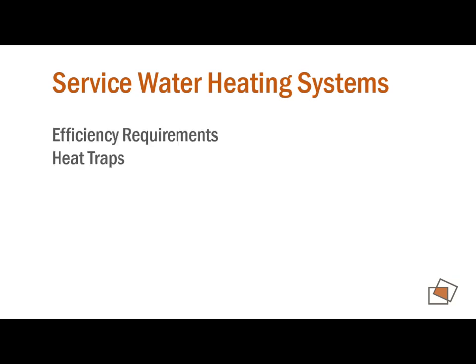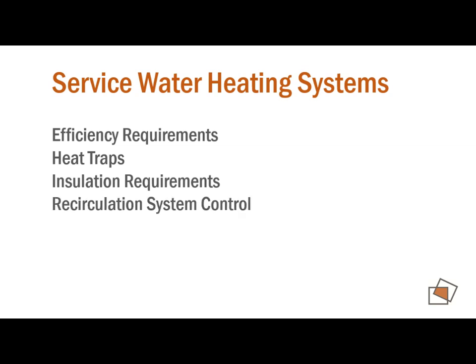Heat traps are devices just to keep the heat from migrating out of the water heater up into the piping system. So these are just a standard fitting. You can do it with a piping loop, but we usually just specify a little fitting that goes on the water heater. Some water heaters even have it built in, but that's a requirement of the energy code. You're required to insulate your hot water piping. So above a certain water temperature, it requires a minimum thickness of insulation. And then recirculation control means you can't just let your recirc pump operate all the time.